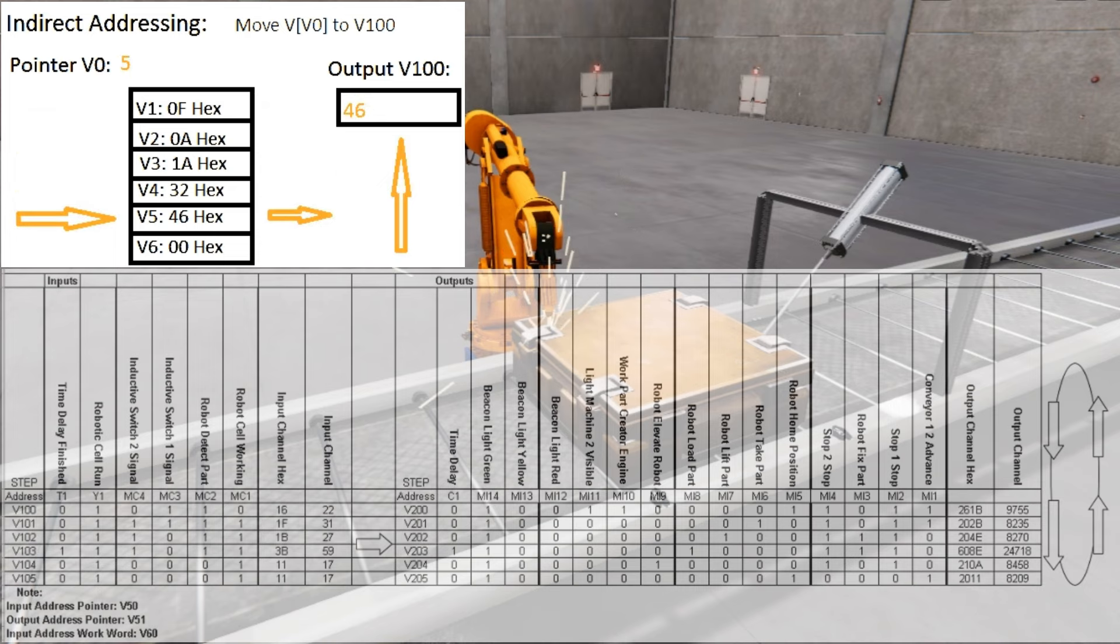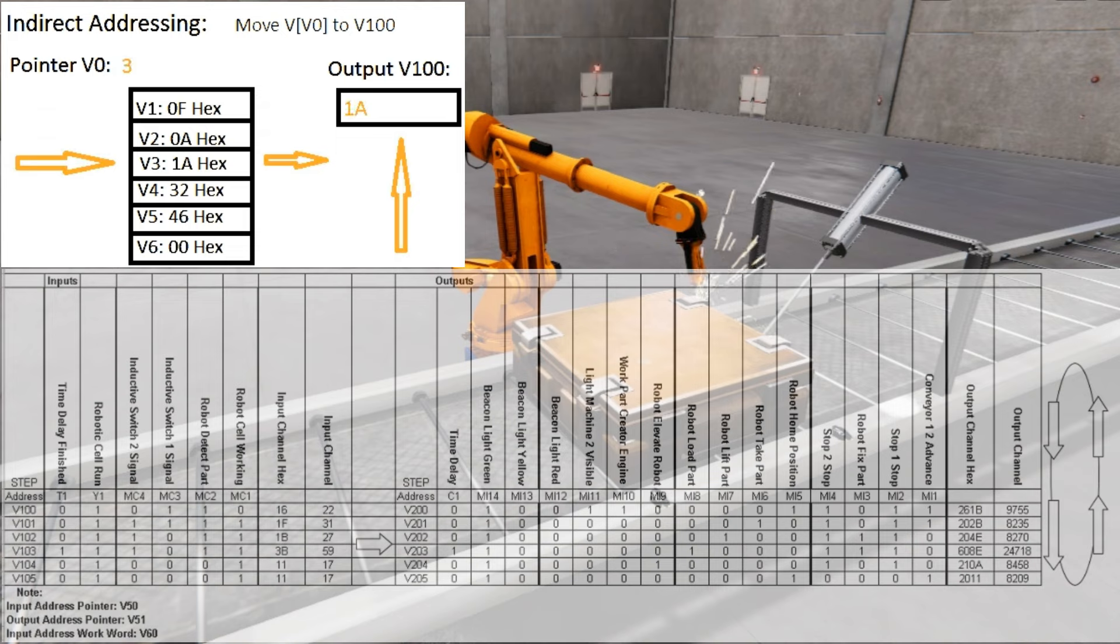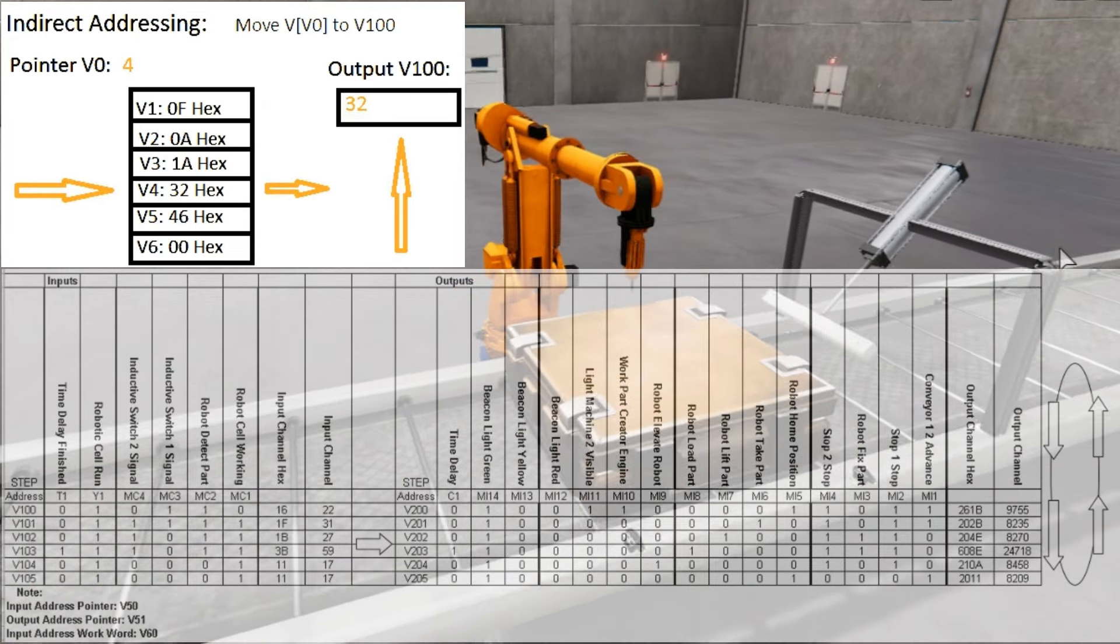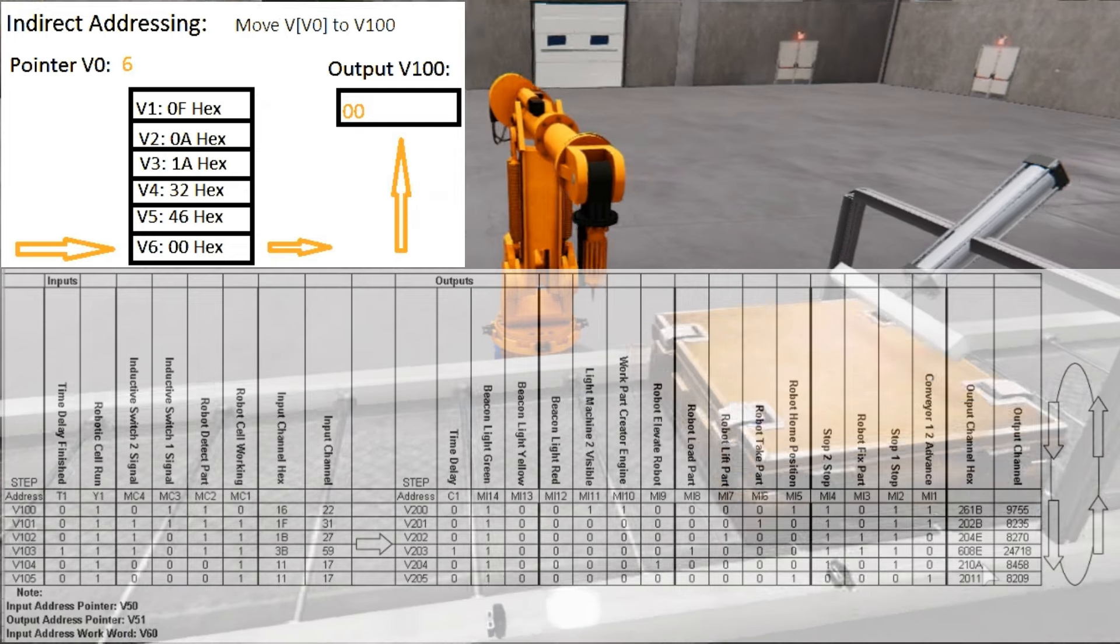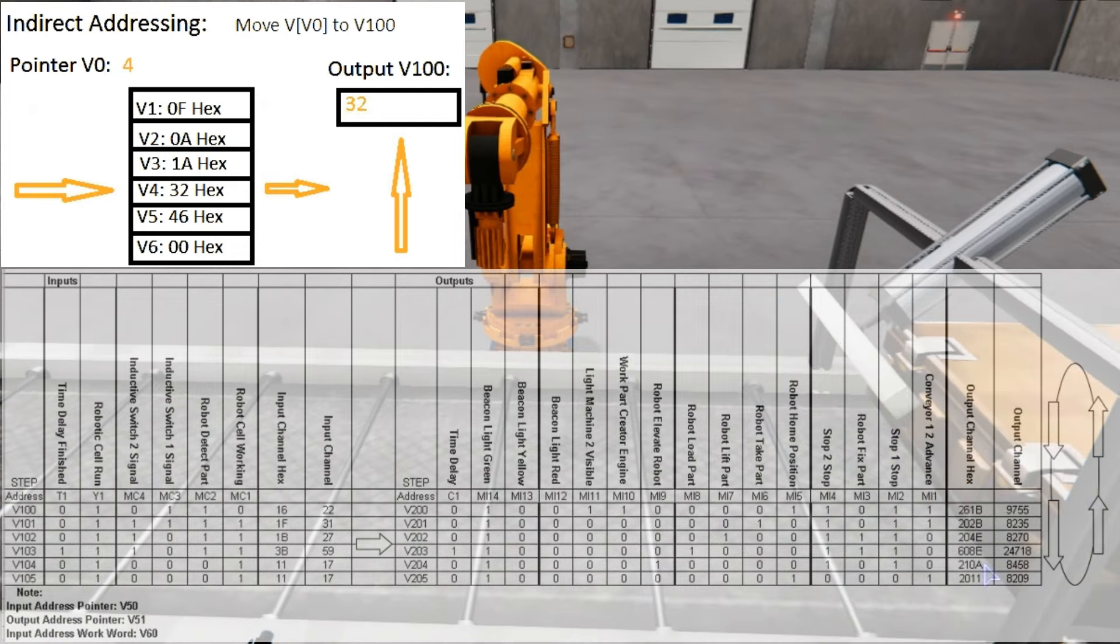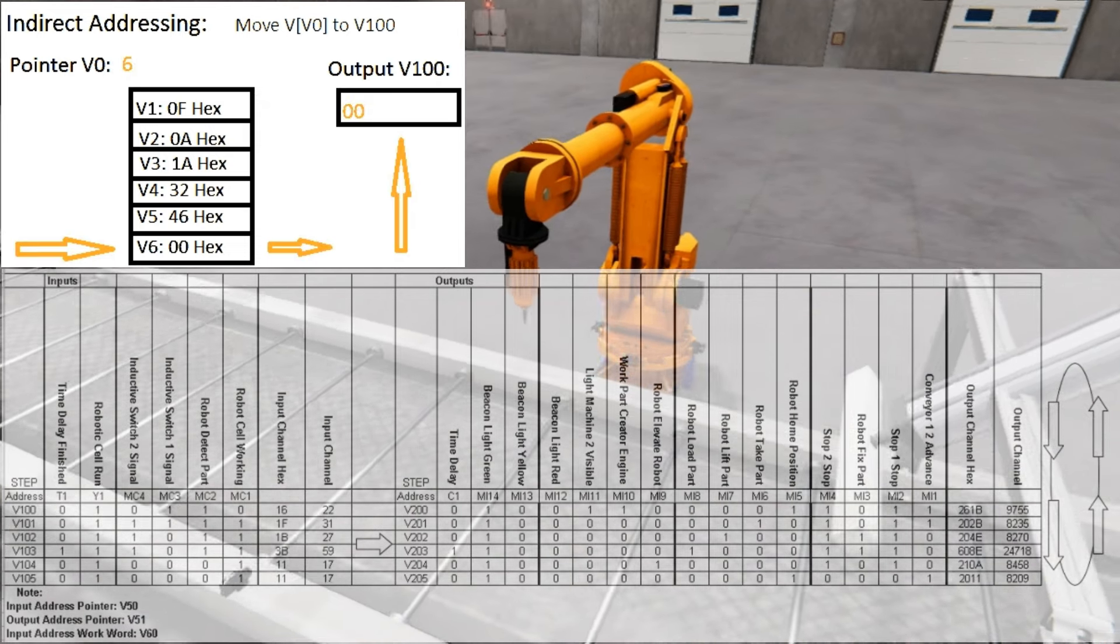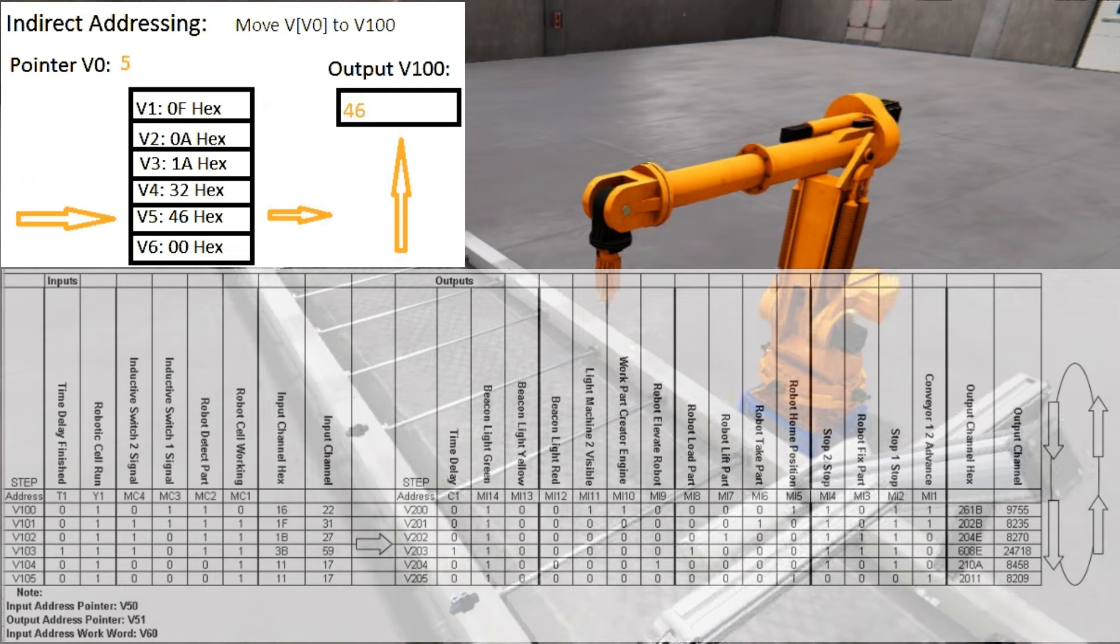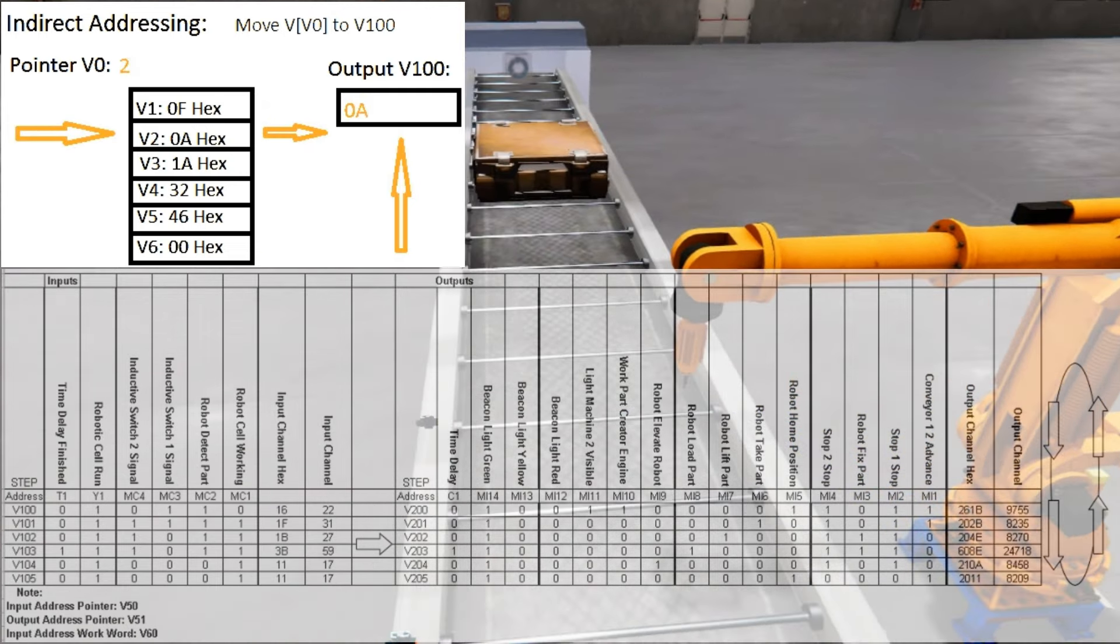Pointers are incremented and the sequence continues. A comparison instruction is used on the last step, and if equal, the pointers are reset, sequencing the machine over again. This powerful method will involve changing the input and output tables to change the sequence of operations. Troubleshooting is quickly done because the pointers show you the table value versus the actual input values.